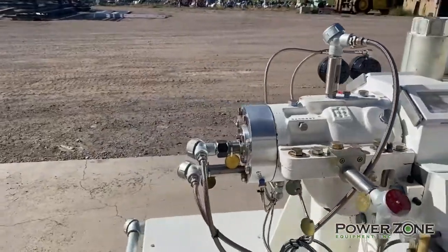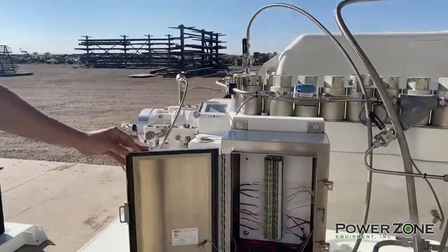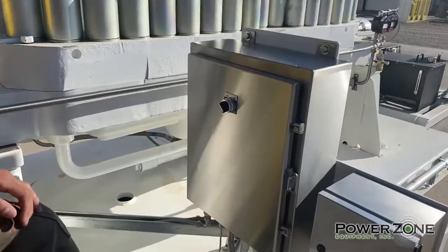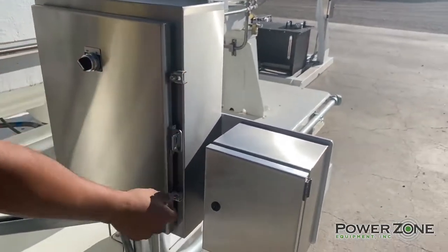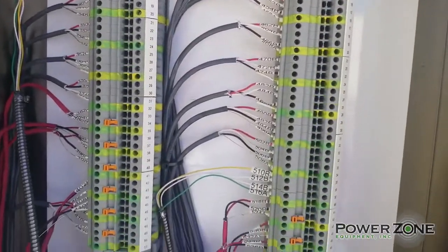The pump features five 100 ohm bearing RTDs as well as metric vibration velocity transmitters. All instruments are routed to a single junction box, simplifying cable tray routing, which in return saves our customer money.